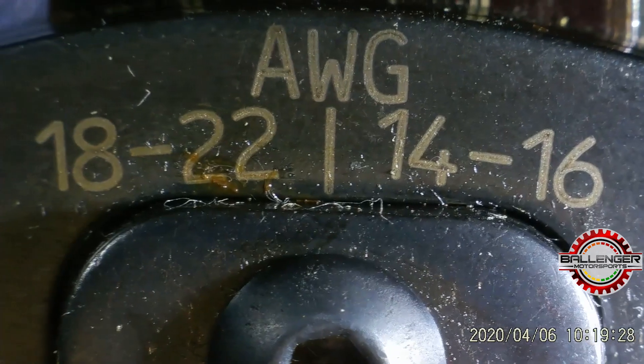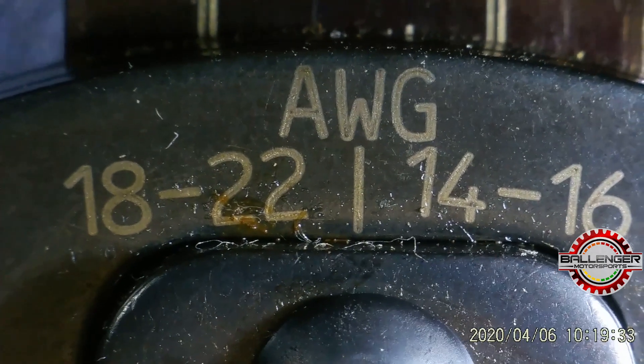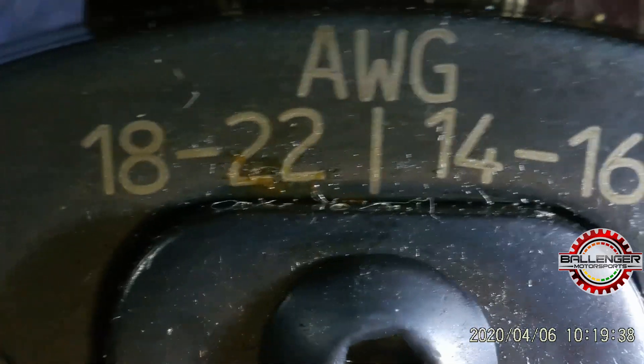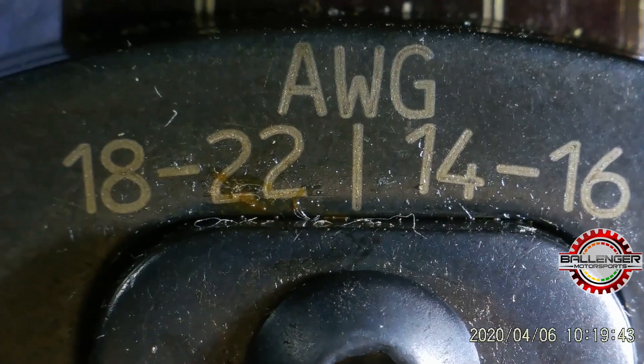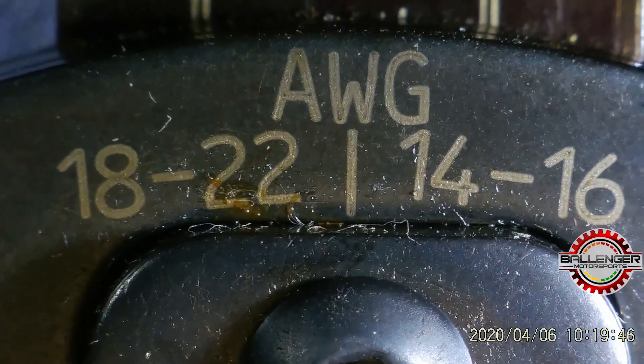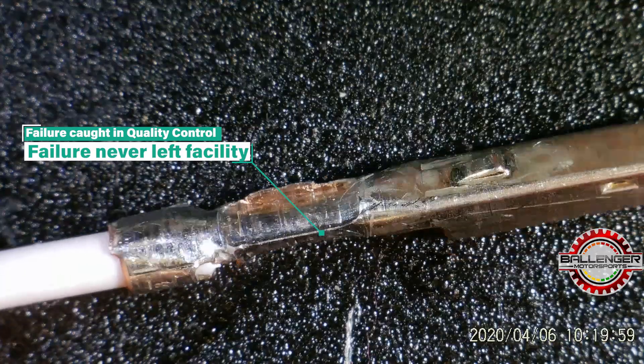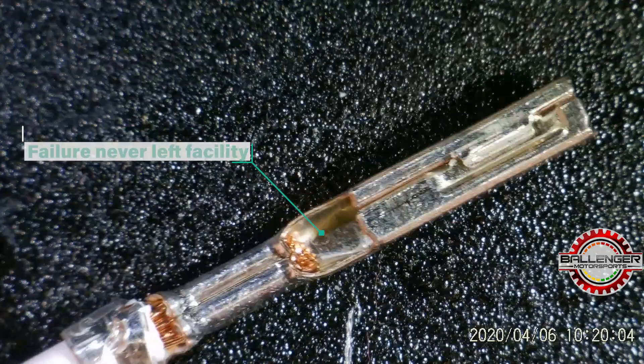Someone simply used the wrong die size, trying to get the insulation crimp to spec, but in doing so they damaged the copper crimp — which is not a compromise you ever want to make. It is much easier to work with the insulation crimp after the fact than to damage the copper crimp. It can't be repaired; that terminal is lost — it is now junk. We cannot pass this. It was caught in QC and failed, and fortunately none of this left our facility. We have a pretty robust QC process here.